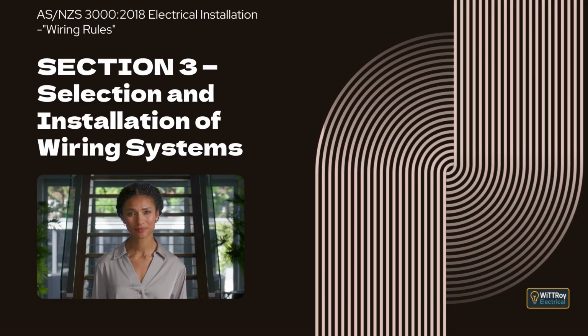The clause also explains that there are limited situations where an enclosure is not required, including where the cable is used as an aerial conductor in accordance with Clause 3.12. Where the cable is installed within an enclosed wall cavity close to an accessory and terminates within 100 mm of the opening, where the cable is inside switchboards or metering enclosures and not exposed to touch during normal operation, where the cable is an earthing or equipotential bonding conductor installed in accordance with Section 5, and where the cable is part of an extra low voltage circuit installed in accordance with Clause 7.5.